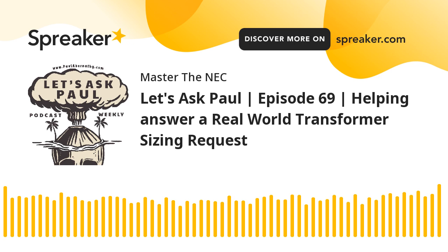It sounds like you want a transformer, and it sounds like you're trying to step the voltage from 480 to 208. A couple thoughts on that before I finish your question part here. If it's 480 volt in the restaurant, I'm sure they have lighting that is not going to be 480. I'm sure there's another voltage in there. Whether this is 480, 277, I have a hard time believing they don't have any 120 volt loads in there. So I'm not sure what this total system is. But when you have 480, it makes me think you have something else in there.